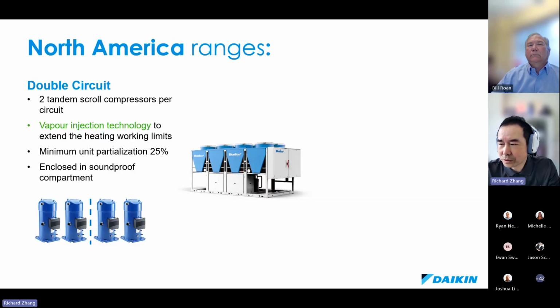Here I'm going to quickly go through some design and product features. No matter how big the units are, 30 or 140, all of them will have a double circuit with 2 tandem scroll compressors per circuit. We use vapor injection technology to extend the heating working limit; right now it's officially 0, but we're pushing for -4. The minimum turndown is 25%.